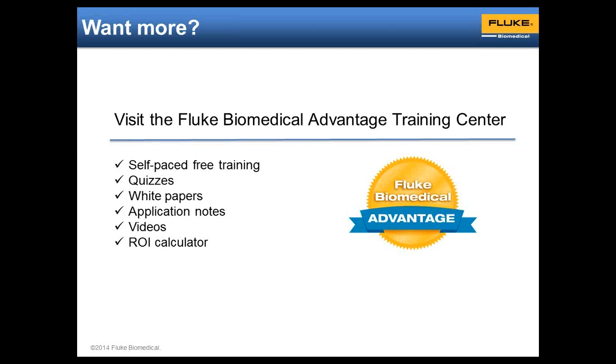Will the new earlobe sensors work on the ProSim 8? So I need to look into that. I believe that they do if they mechanically fit. The problem is sometimes the sensors, when they get too small, can't fit across the sensor or the emitter. So it really depends on mechanical fit at that point, and then again make sure that we have the right R curve for that manufacturer.